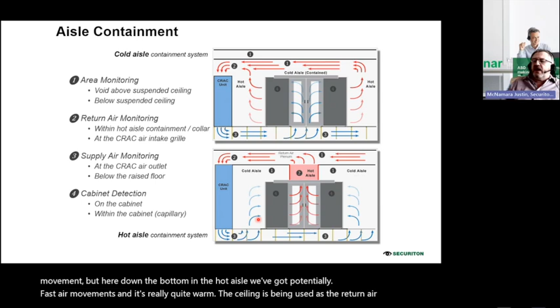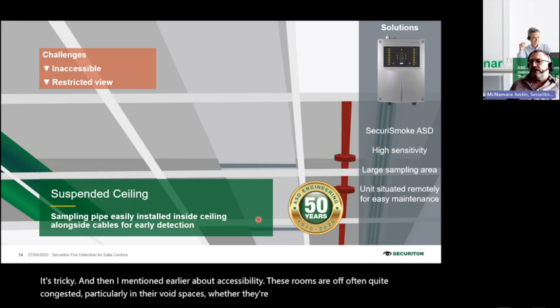It's tricky. And then, as I mentioned earlier about accessibility, these rooms are often quite congested, particularly in their void spaces, whether ceiling or floor. They will be congested with cable trays, cables themselves, pipes for cooling, lighting, and other forms of monitoring. They're congested spaces, and accessing them is very tricky, even if accessing the data center area itself is permitted.